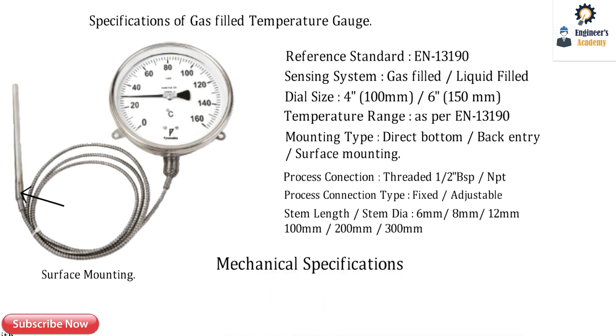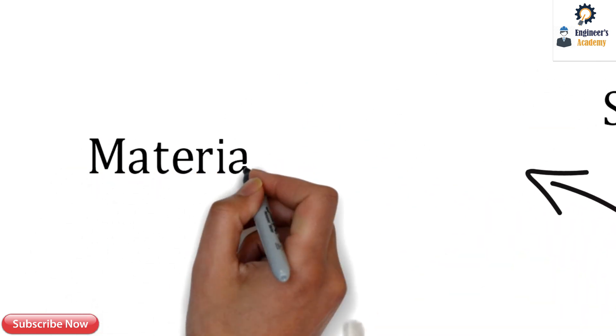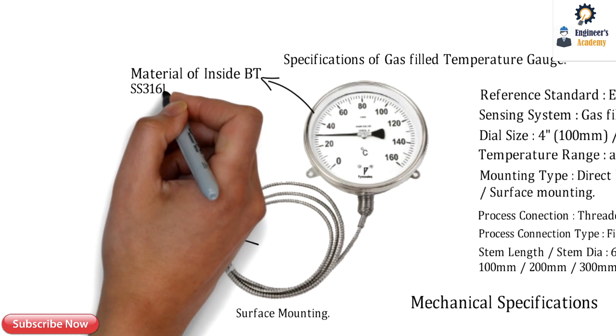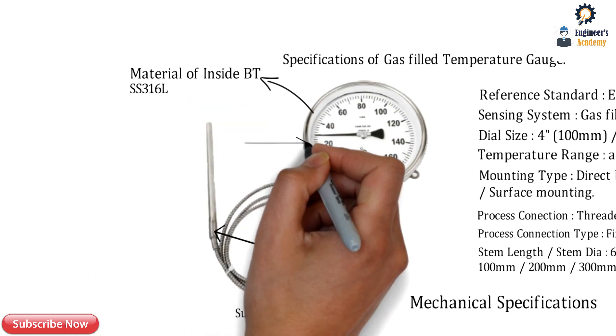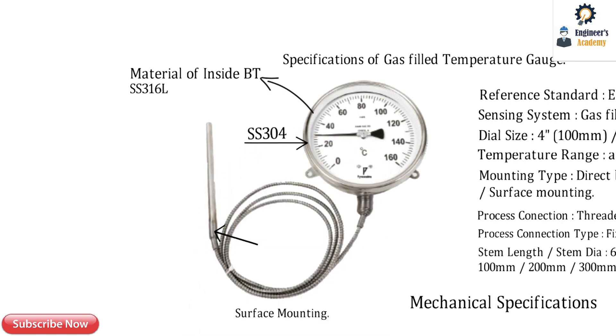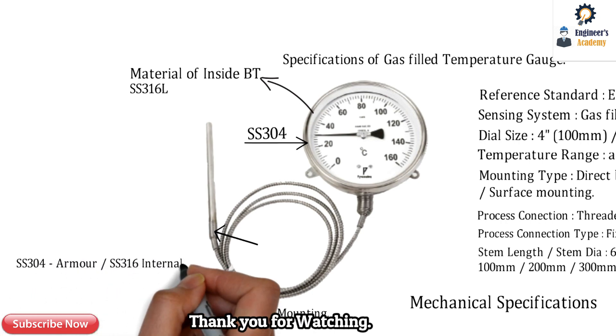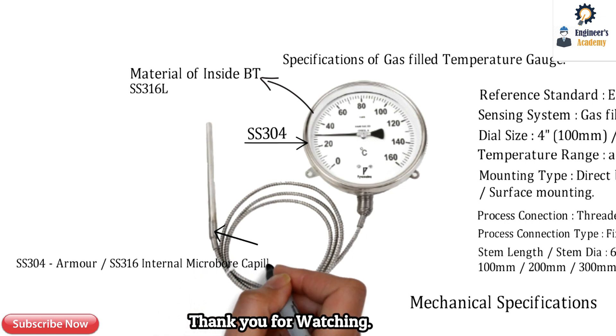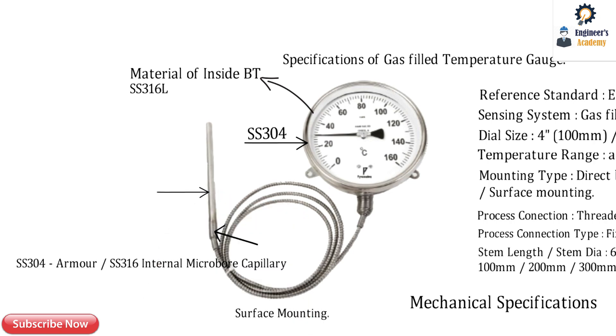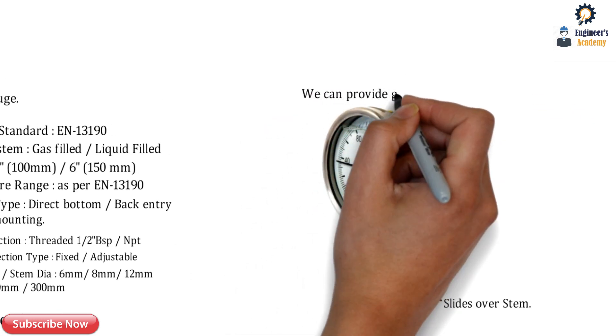These are the mechanical specifications of the temperature gauge. The material of the internal Bourdon tube is SS 316L, which also comes under the specifications. The case and bezel material is SS 304, or SS 316L depending on the requirement. The armor material of the capillary is SS 304L, whereas the microbore capillary uses SS 316L. The stem material is always SS 316L.